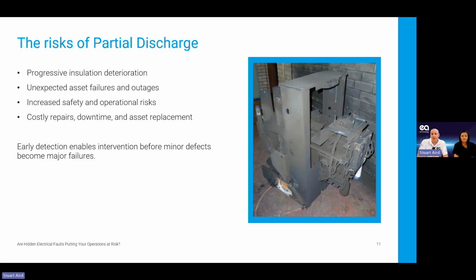And ultimately, we can save some money as well if we prevent a costly failure and downtime, and we can plan our asset replacement as well. So if we trend our PD activity, or we put things like monitors in, which we'll talk about in the next section, we can extend asset life, and we can also pick up things that prevent those failures and costly repairs. So early detection will enable intervention before any minor defects become major failures, and you end up with a circuit breaker that looks like this on the picture. And I'll pass back over to Cheryl.